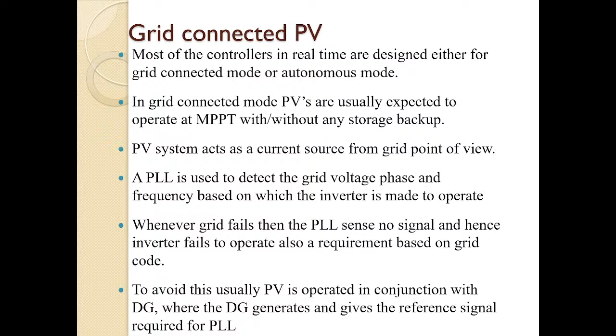So in multiple cases, you may see that the photovoltaic system on the rooftop of an academic building does not work when the grid fails, and we need to operate a diesel generator set which will synchronize with the system, and the photovoltaic will start producing power along with the diesel generator. The diesel generator cannot absorb the photovoltaic power. Hence, it will always go into the load side, or the consumption has to happen. And hence, there will be a requirement to coordinatedly operate the DG and PV in a proper way so as to make the system stable.